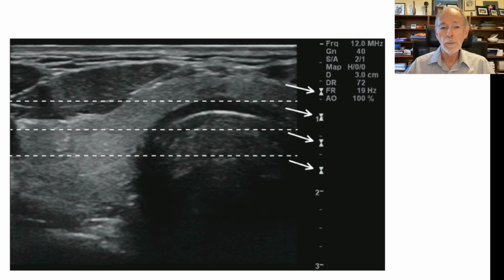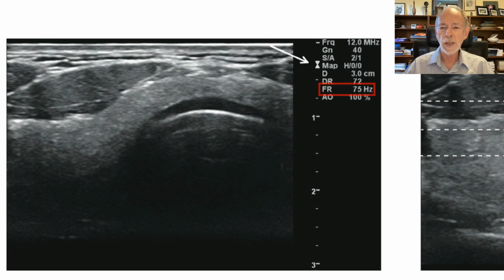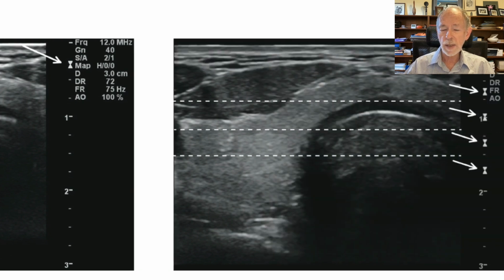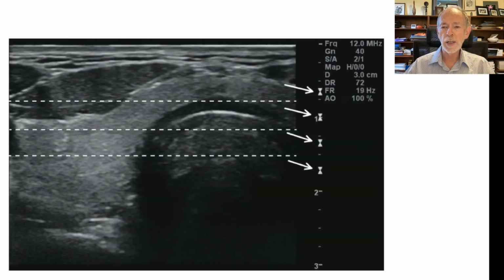So whenever you use multiple focus rather than just a single focus, you're actually acquiring the image in strips, as shown here, and this means it's going to take longer to acquire. In fact, it will take 4 times as long to acquire this image because of the 4 focuses. If we have a look on the left, we see that the frame rate is 75 Hz, which means 75 frames per second. A very good high frame rate, which is what we'd expect for such a superficial area. On the right-hand side, where we're using 4 focuses, the frame rate has dropped to 19 Hz, which is approximately 1/4 of the original frame rate of 75.